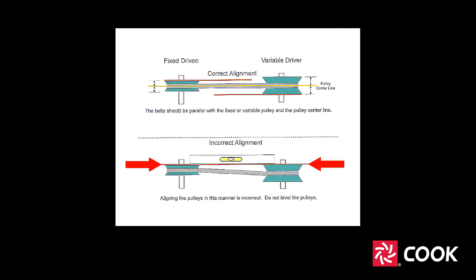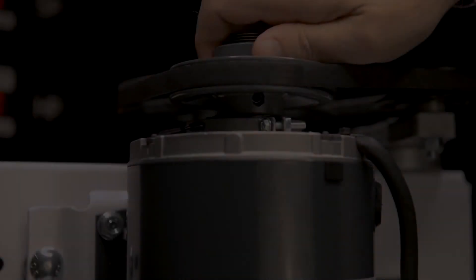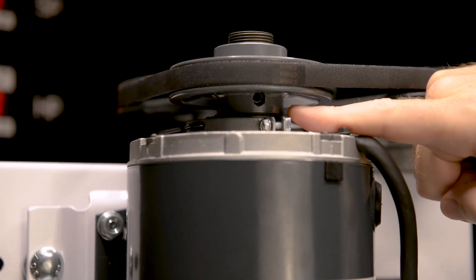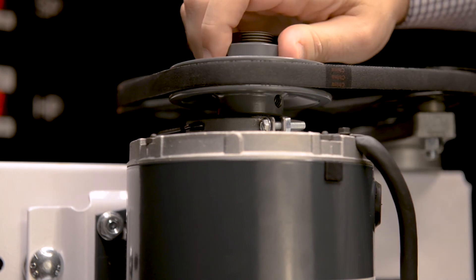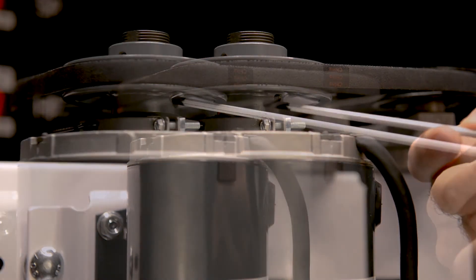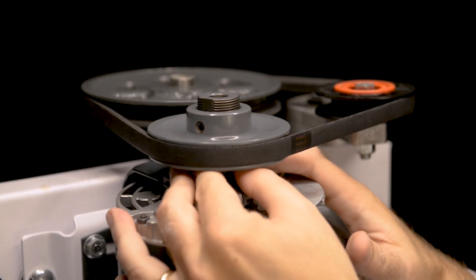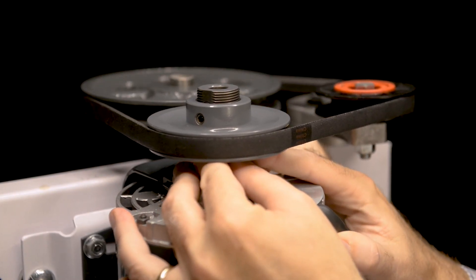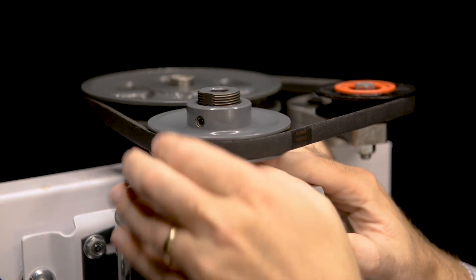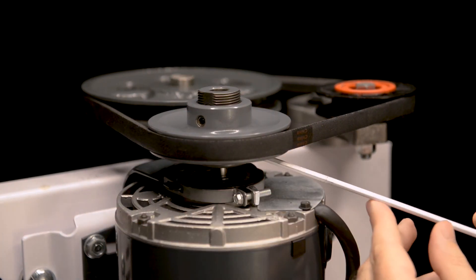To adjust the motor pulley for proper alignment, locate the set screws on the bottom side of the pulley. Some pulleys will only have one set screw while others will have two set screws. Loosen but do not remove the set screws. Raise or lower the pulley to achieve the proper belt alignment, visually checking that the centers of the pulleys are in alignment. Tighten the set screw per manufacturer's guidelines.